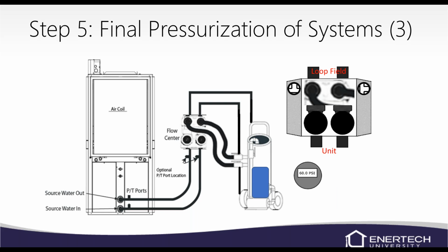And obviously, we've got to have some pressure so the pumps don't cavitate. So we could drop down to 20 PSI, 10 PSI. Probably really wouldn't want to see it a whole lot less than 10. But just know we have to have some pressure, and we don't want it to be above 100 psi, and obviously nothing below about 10 on a pressurized system. So I don't ever see them at 100. It's usually somewhere in that 40 to 60 range is what I see.